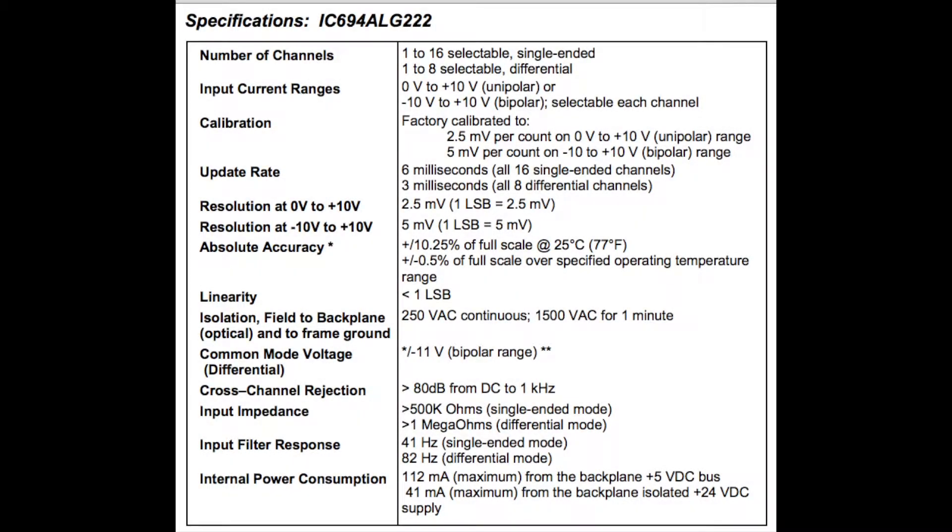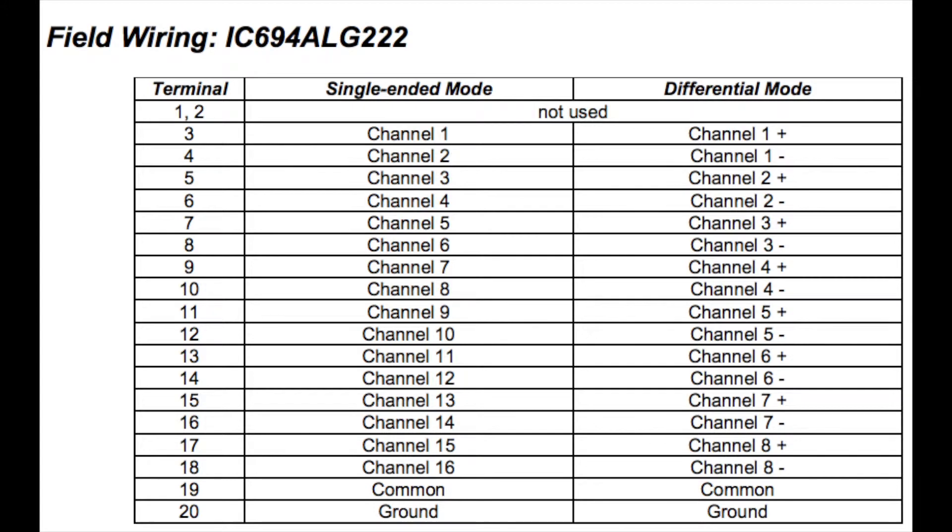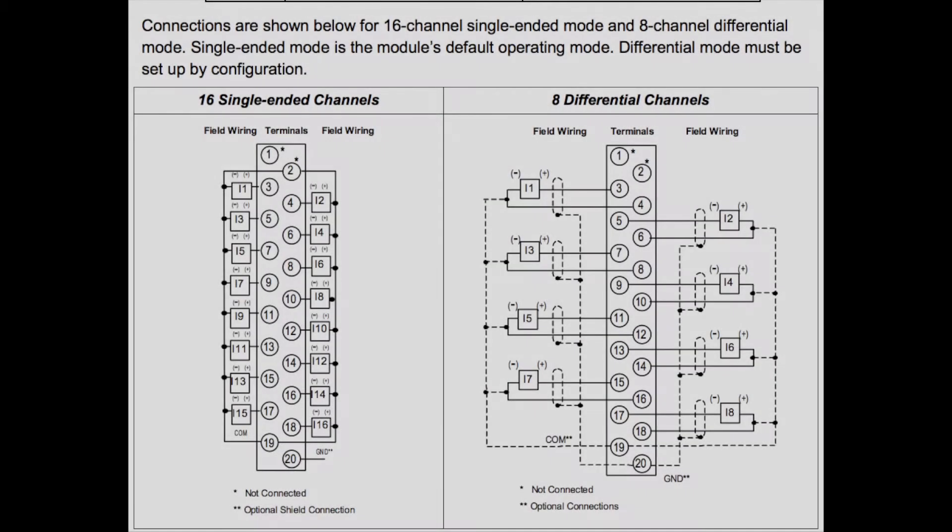This card is capable of reading from negative to positive 10 volts DC. What's special about it is you can choose from 16 channel single-ended voltage DC inputs or 8 differential voltage DC inputs, depending on your purpose. There are two different wiring diagrams that go along with that.